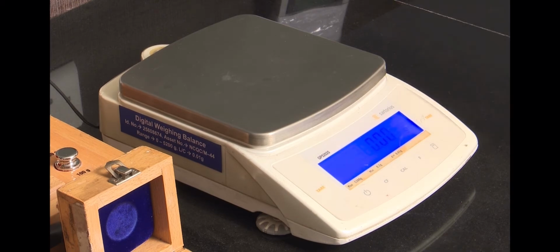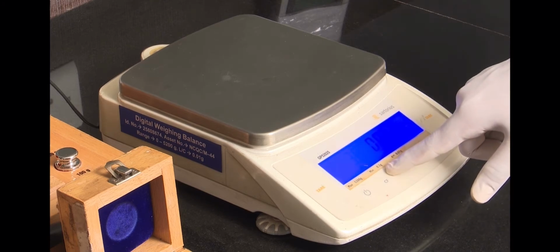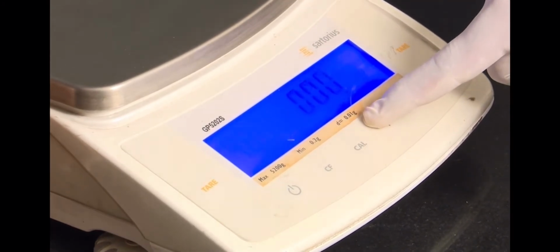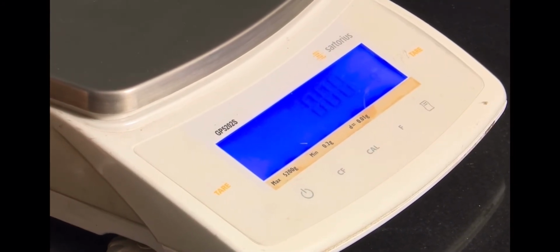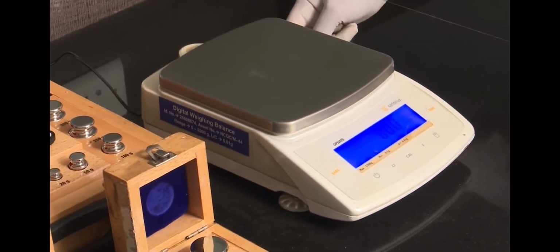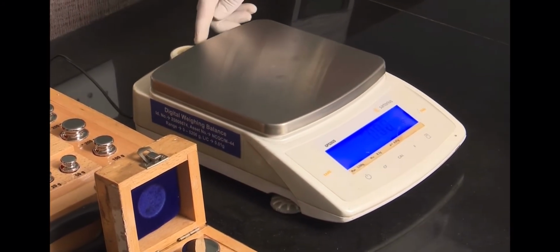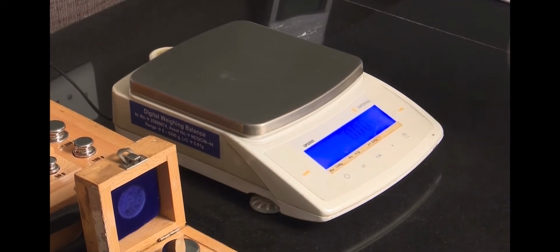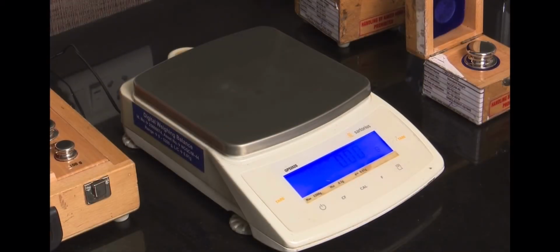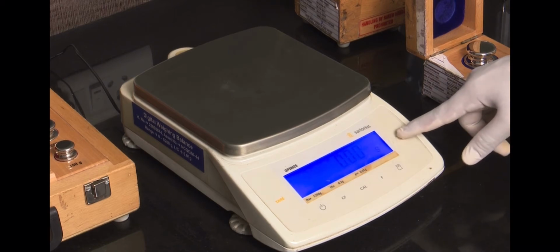This is a digital weighing balance having range 0.2 to 5200 grams and 0.01 gram resolution. This is called pan. This is leveling screw. And this is display of the balance. Leveling screw is used for leveling of balance. Before proceeding for calibration, ensure that the balance is leveled properly. Keep the balance to stabilize as per the balance internal process. Now press the tare button and make the reading 0.